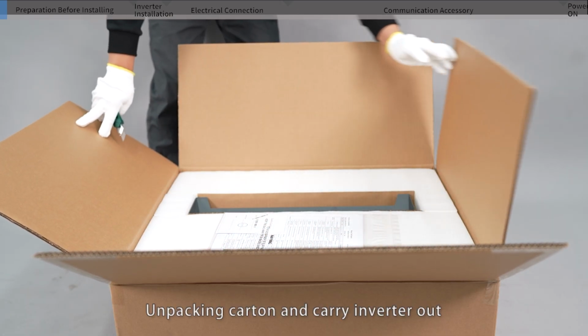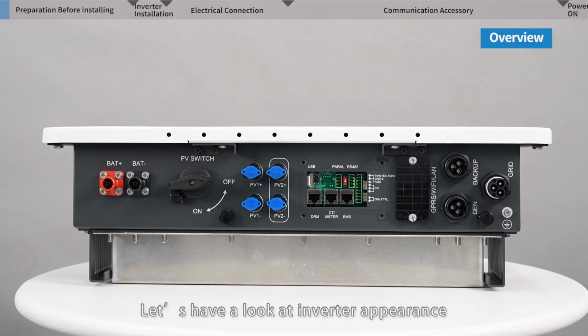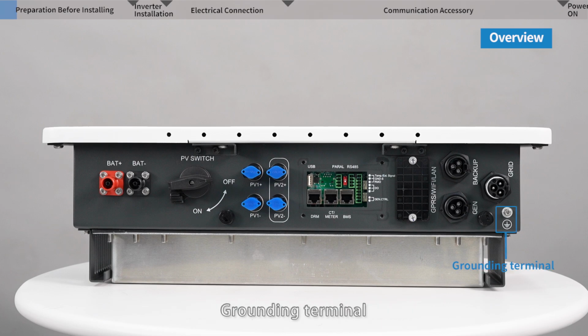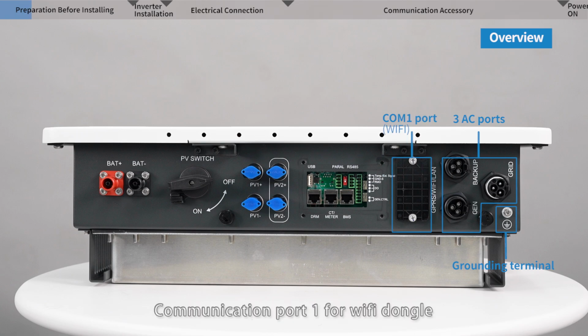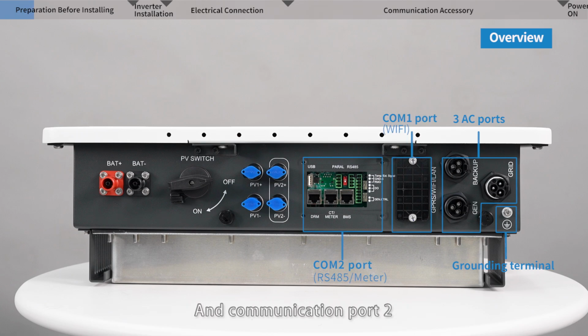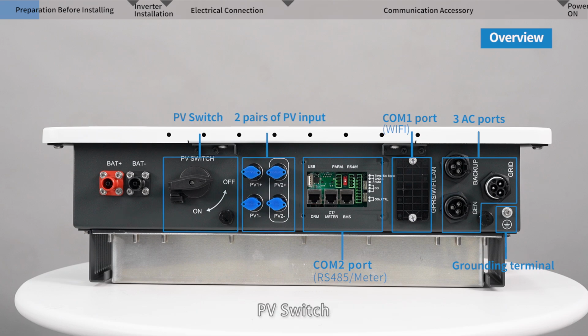Unpacking the carton and carrying the inverter out. Let's have a look at the inverter appearance and connectors first. On the bottom side, we can find the grounding terminal to install the grounding cable, 3 AC ports for connection of grid, backup load, and generator, smart load, or on-grid inverter, communication port 1 for the Wi-Fi dongle, and communication port 2, 2 pairs of PV input, PV switch, and battery port.